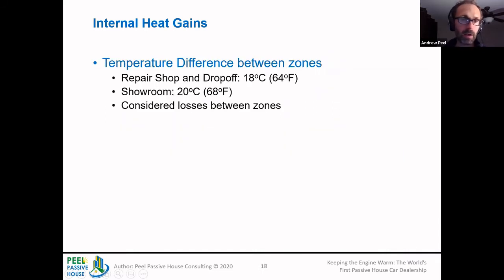We also had a temperature difference between the zones. The client had requirements to heat the showroom to 68, whereas the repair shop and the drop zone were a bit cooler, because the workers like it a bit cooler since they're moving about most of the day. The drop zone didn't need to be quite as warm as the showroom either, because again they're generally moving about in that space. So we did have to consider the heat loss between the zones because of this temperature difference. It's not a huge amount, but it's important to keep in mind in the balance.